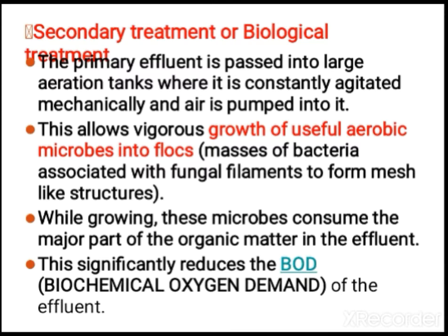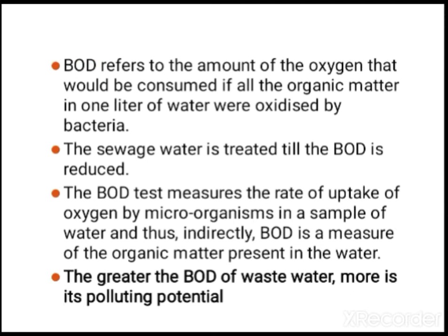While growing, they consume the organic matter in the effluent. So it significantly reduces the BOD, biochemical oxygen demand, of the effluent. The microbes digest the organic matter and need oxygen, and for that purpose we provide oxygen by means of aeration. BOD is the amount of oxygen needed, and it depends upon the organic matter present in the polluted water.